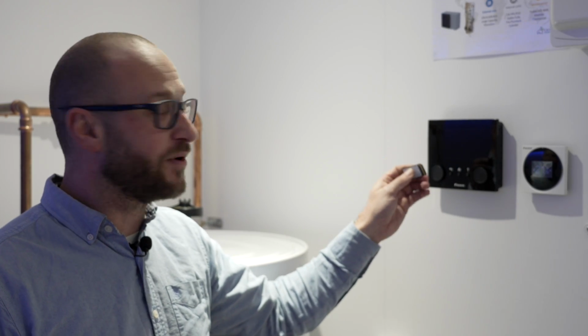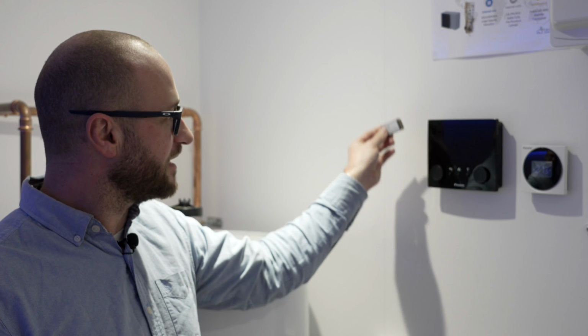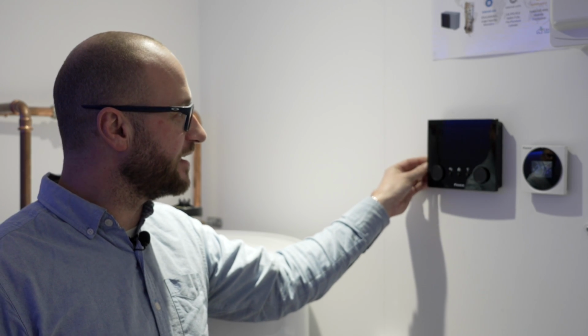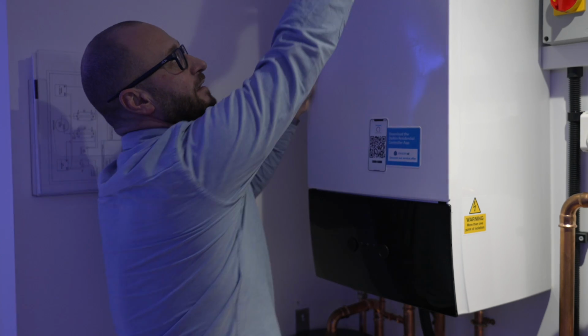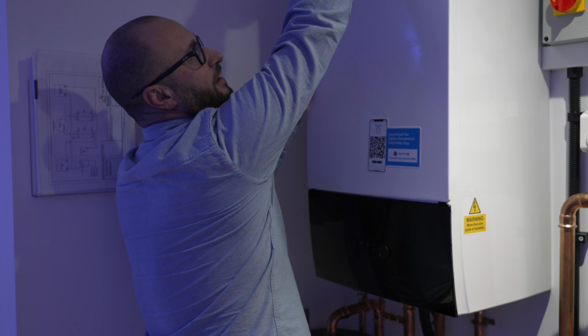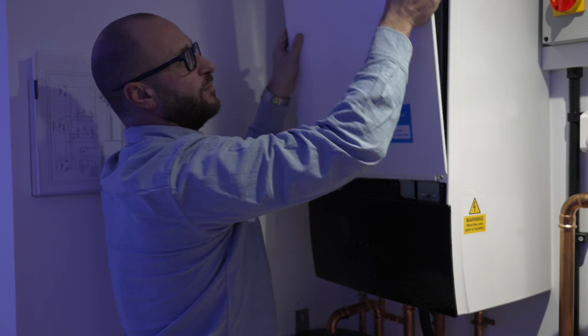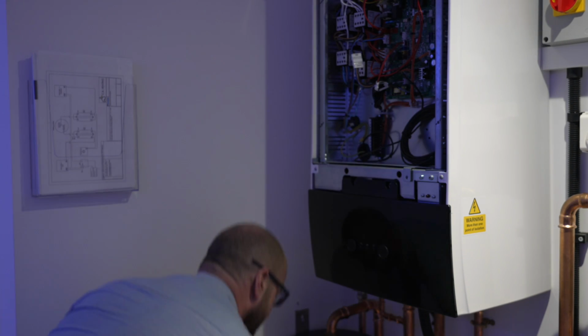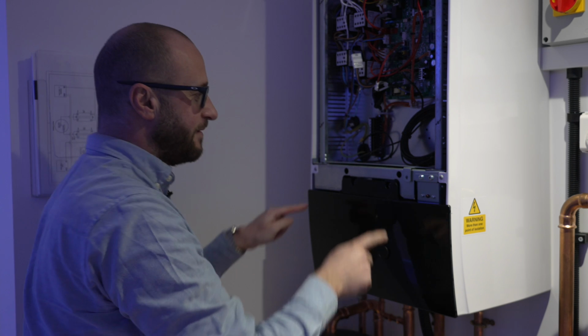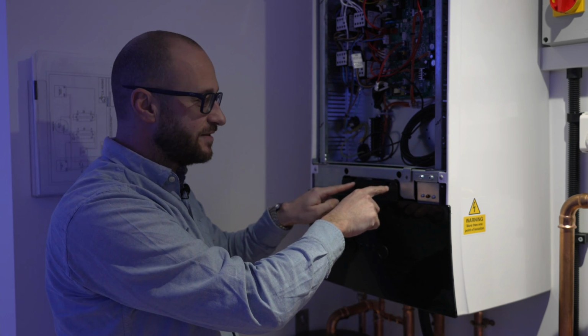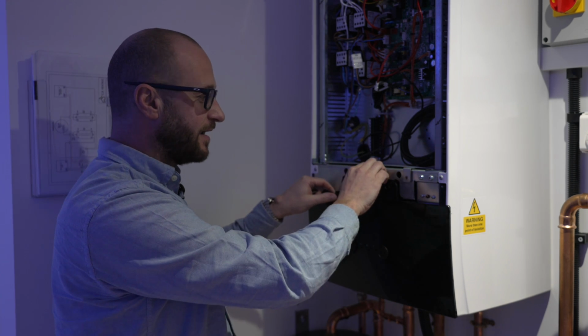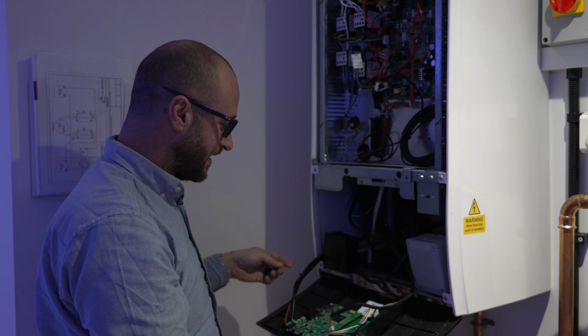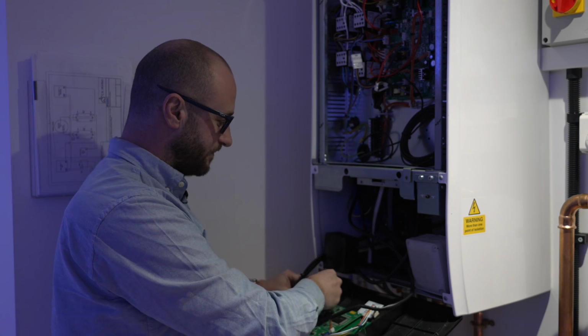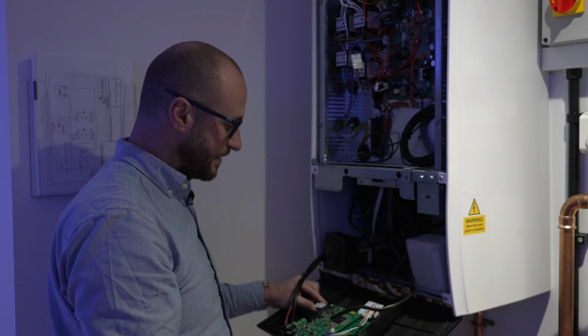If you've got a monoblock, you'll have an MMI screen in your home somewhere, and your LAN adapter slides into a slot in the side. If you've got a hydro box, there's a little twisty screw on the top, and you pop the front off. You will then find two retaining screws here, little Phillips screwdrivers. Once they're undone, this front will pop down and you'll find a little slot to put your LAN adapter at the bottom.